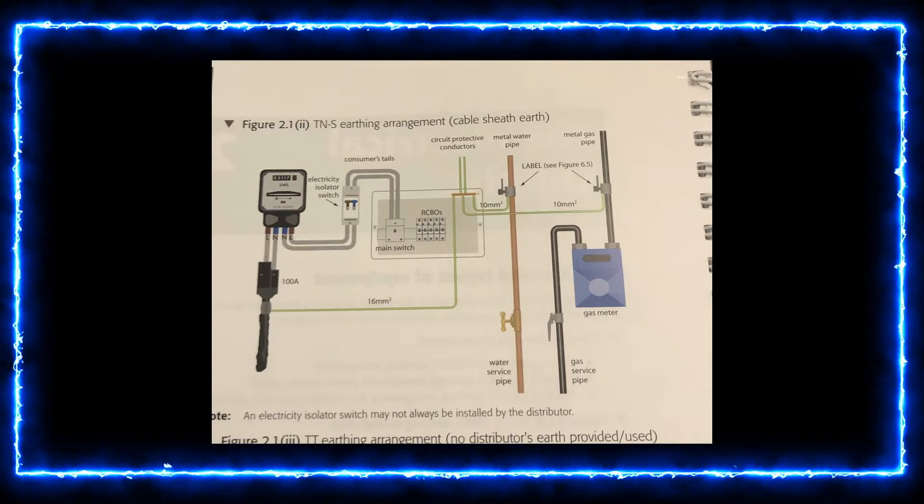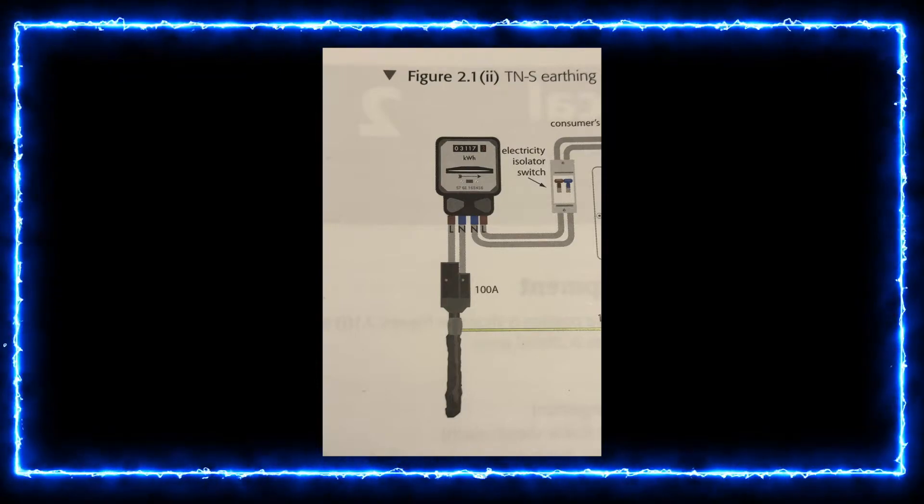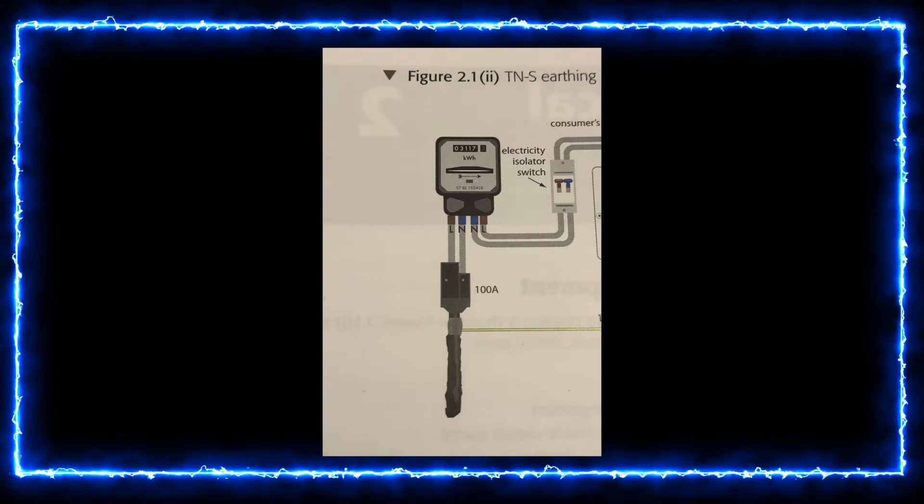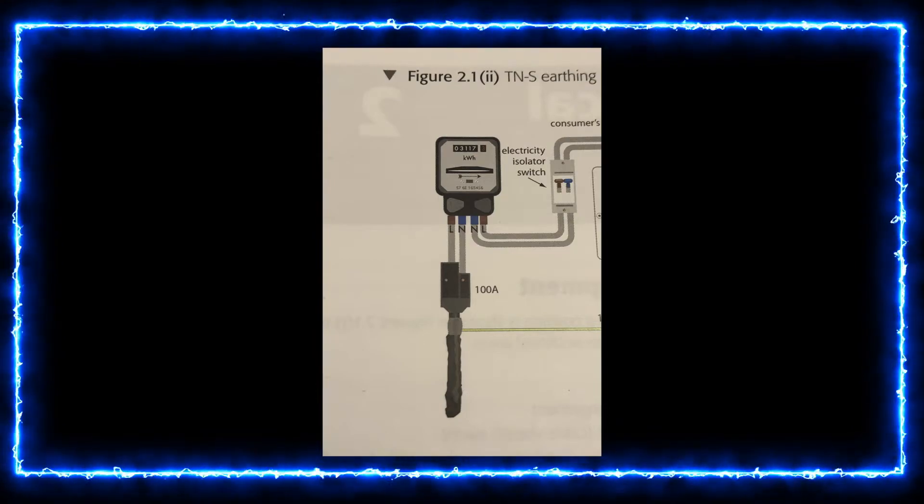On this drawing you'll see that the earth conductor connects directly onto the supply cable, and this is how you'll tell that you're looking at a TNS earthing system.